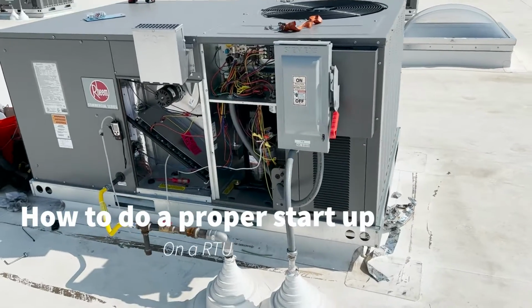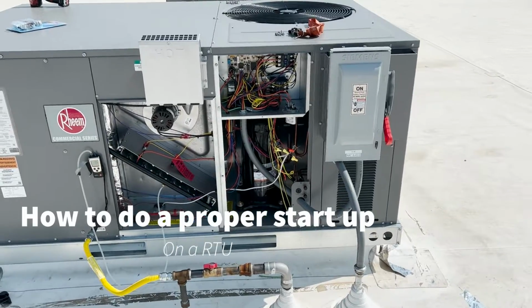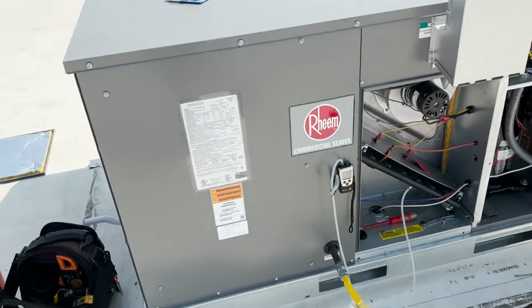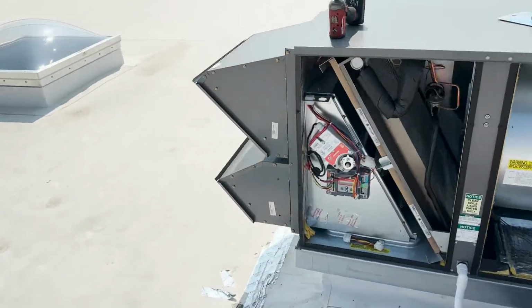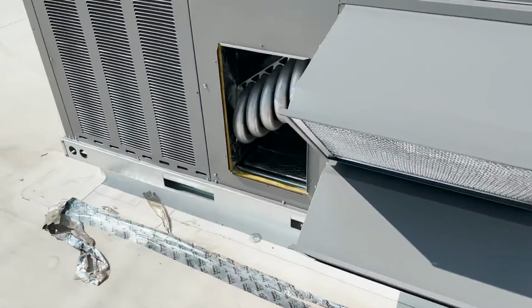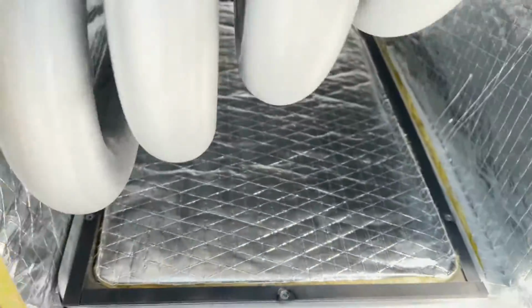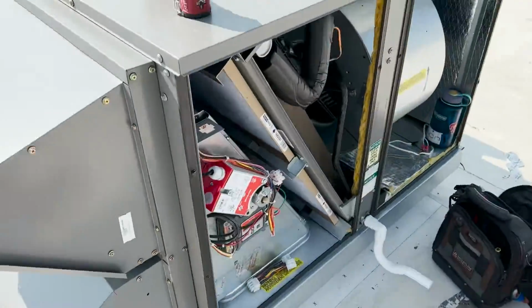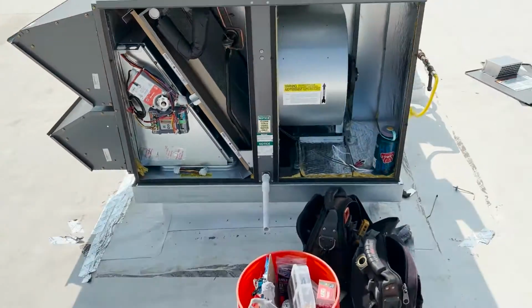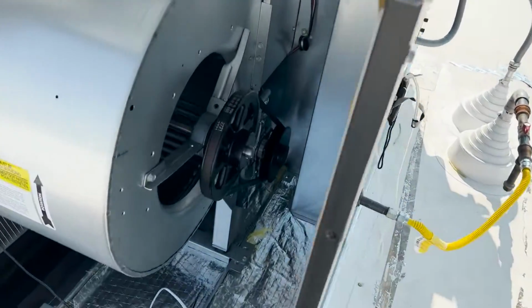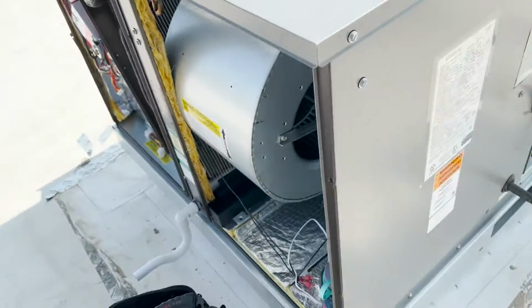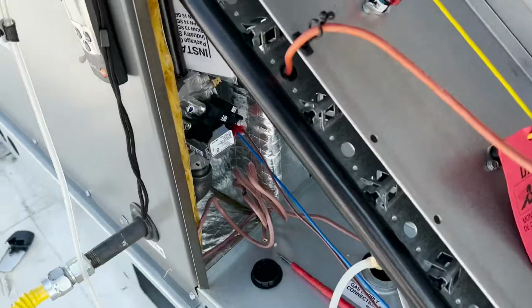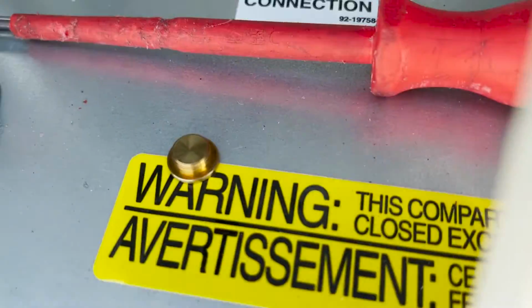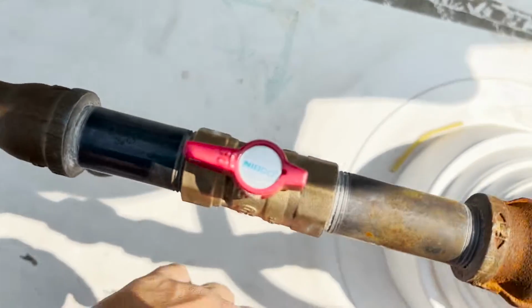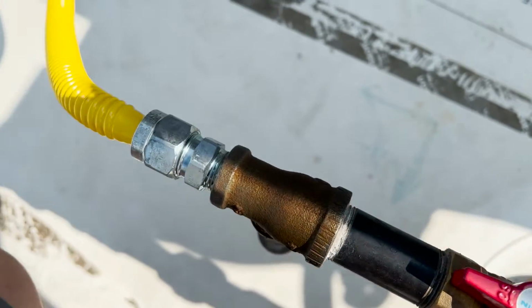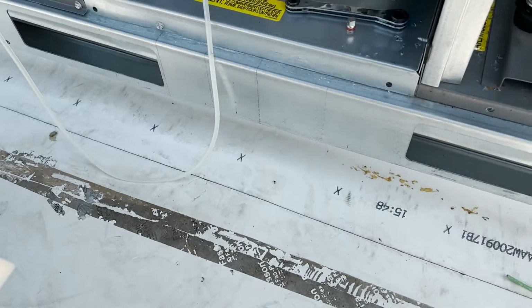All right, let's talk commissioning real fast. So step 1, walk up and you're gonna pull your control panel, your gas panel, both blower doors, and our burner compartment. And then the burner compartment door, we're gonna put inside the unit. Over here, before anything's lit up, we're gonna check that our motor key is set, that all of our bolts and nuts on our moving pieces are good. We're gonna turn our gas valve on, open up our cap on our adjustment port, turn on our gas. So if it does leak, we have a few minutes to kind of smell it before we fire it.